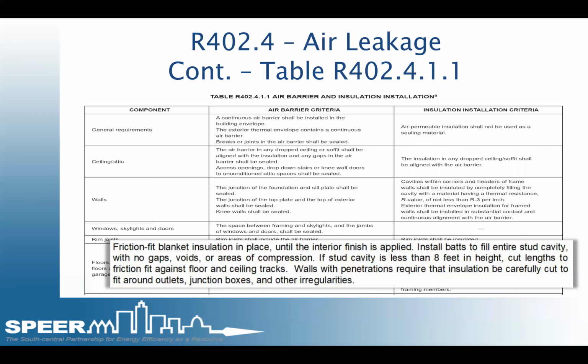So this is showing us a snippet of the table of R402.4.1.1. It states the components of the building thermal envelope as indicated in the table shall be installed in accordance with the manufacturer instructions and the criteria indicated in the table as applicable to the methods of construction. Where required by the code official or a third-party verifier, all components shall be inspected and verified compliant. This table describes how each component is to be air sealed and insulated. It's like a checklist that you could carry around with you if you wanted to print one out.